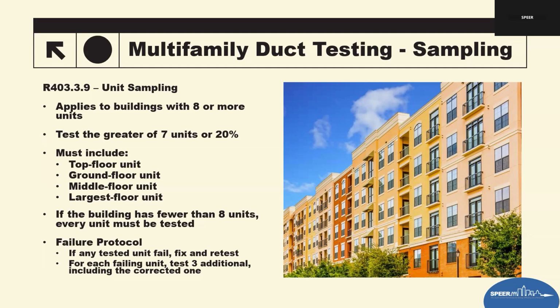So what happens when one fails? If a duct test is failed, first of all, that one needs to be corrected and retested before it can pass. But more importantly, when one unit fails, the code now requires us to expand the sampling by testing 3 additional units, including the one that was just fixed. This continues until all units in the expanded sample pass. The idea is to catch systematic installation problems early and ensure fixes happen across the building, not just in one unit. So sampling saves time and cost, but if the sample unit doesn't pass, the testing expands quickly and can get expensive. Good duct installation practices up front basically keep this from becoming a problem.